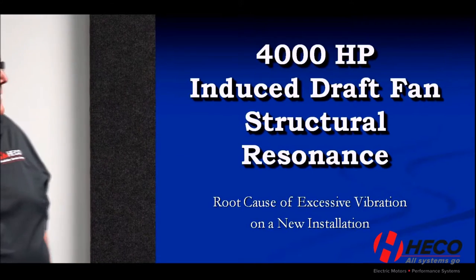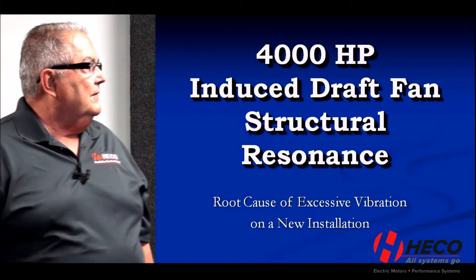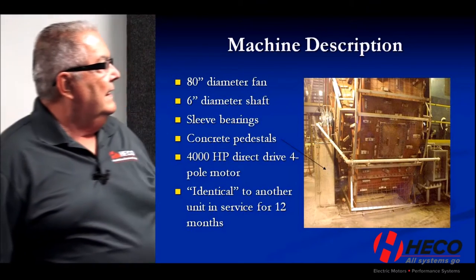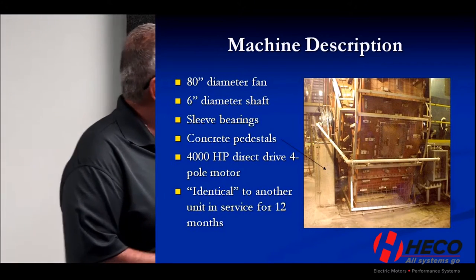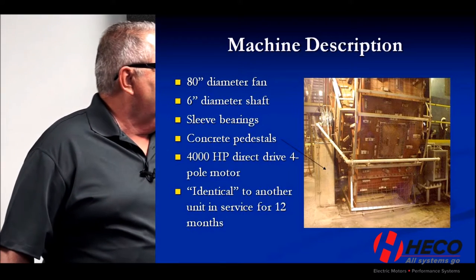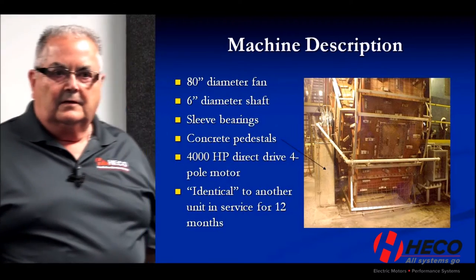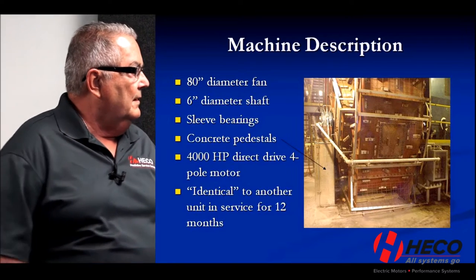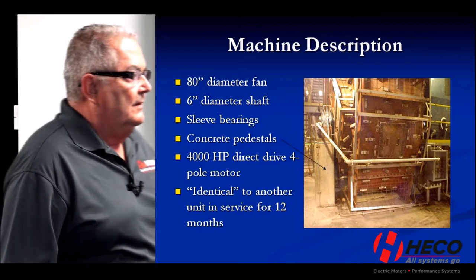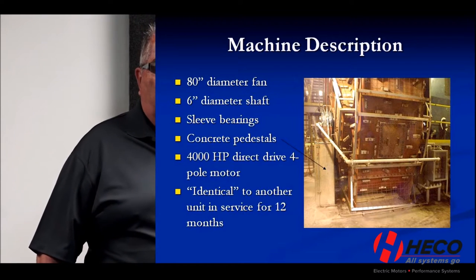The first case is a 4,000 horsepower induced draft ID fan that had a structural resonance. It's an 80-inch diameter fan — there's a picture of it — with a 6-inch diameter shaft, sleeve bearings, concrete pedestals, direct drive to a four-pole motor running around 1,800 RPM. It's identical to another unit that has been in service for 12 months. This was a plant that was expanding, and the first fan came in, was commissioned, and ran fine with no problems.